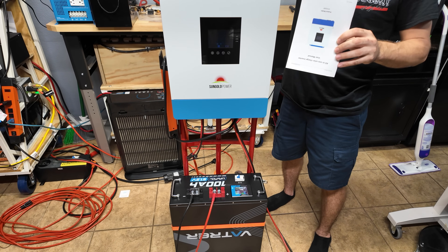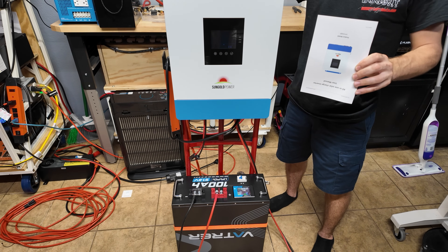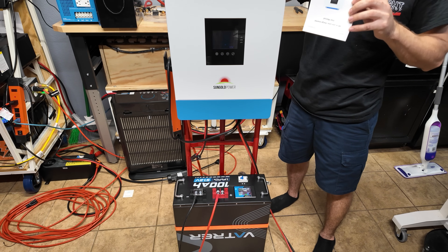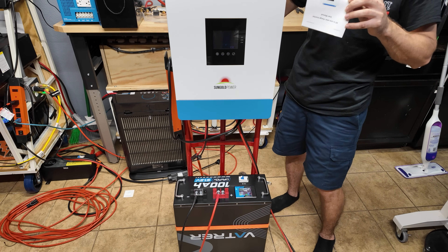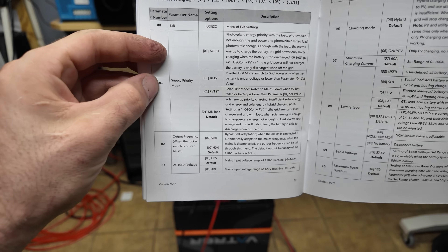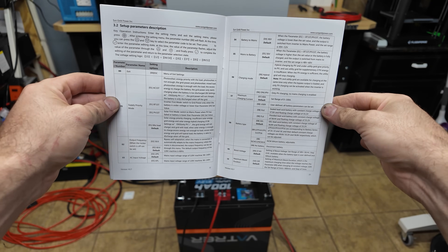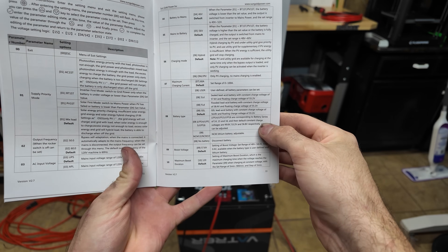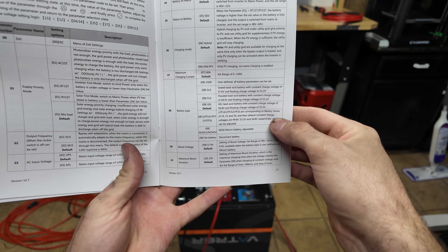The next thing I'm going to do is go through the manual and make sure I have this set for the correct battery type. I'm not using any battery communication — I never do on any of my setups — so we're just going to set it to normal 48-volt lithium iron phosphate. We need to make sure the low-voltage cutoff and high-voltage cutoff are set correctly. Out of the box the inverter is set for gel battery mode with a charge voltage of 56.8V and a float voltage of 55.2V.